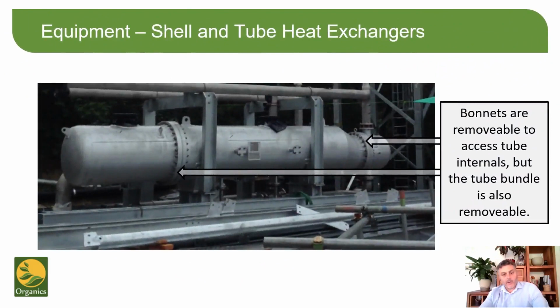The high-pressure hot water circuit takes the heat from the economiser and feeds it where necessary. Generally, this will be to 1 or 2 heat exchangers that provide final stage heating for the process air and the wastewater. We use shell and tube heat exchangers to generate steam when necessary and as the main heater for the incoming wastewater. Again, material selection is fundamental, as we have found that longevity of service is of utmost importance.